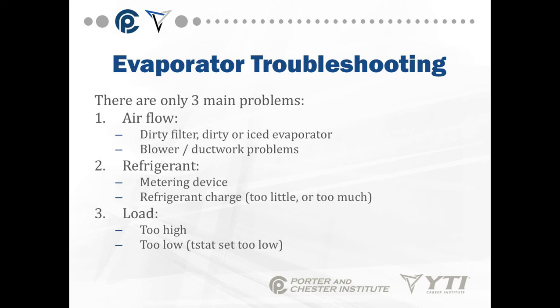Evaporator troubleshooting comes down to three main problems: airflow, refrigerant, and load. Airflow issues include dirty filters, dirty or iced evaporators, and blower or duct work problems. Refrigerant issues include metering device problems and refrigerant charge. Load can be too high or too low.